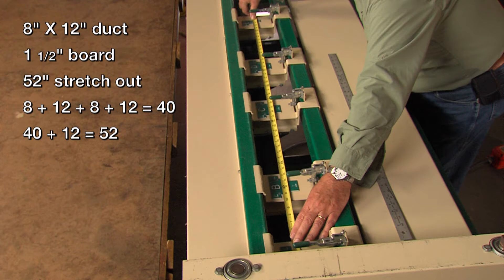For this 8x12 duct with one and a half inch board, we are looking for a 52 inch stretch out from the stop on the left to the cutoff tool on holder E. To get that number, we added the inside measurements: 8 plus 12 plus 8 plus 12, which equals 40, and add another 12 inches.